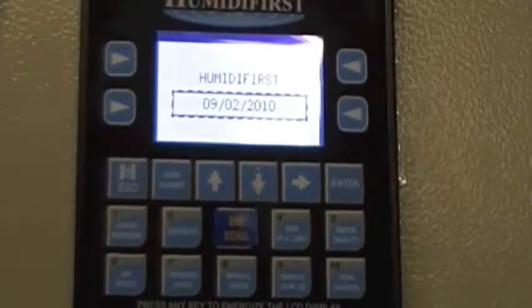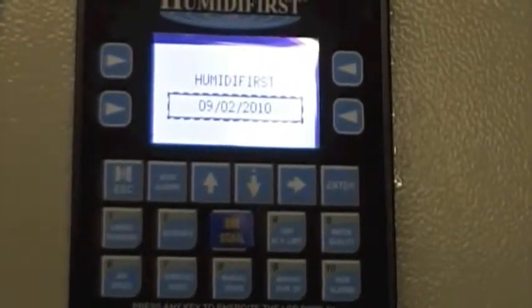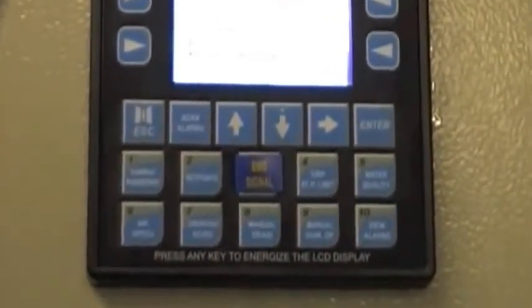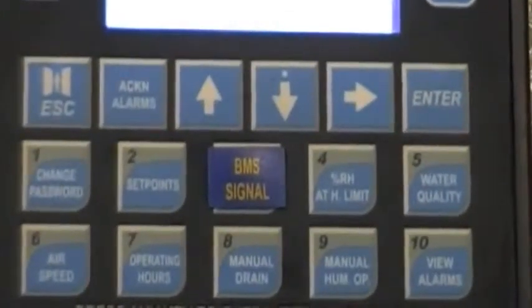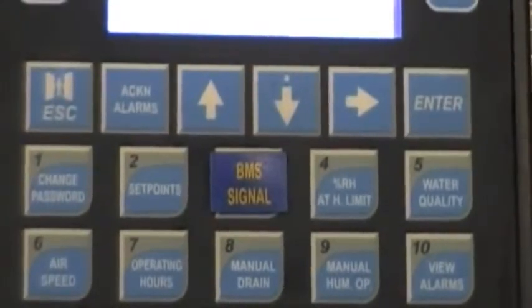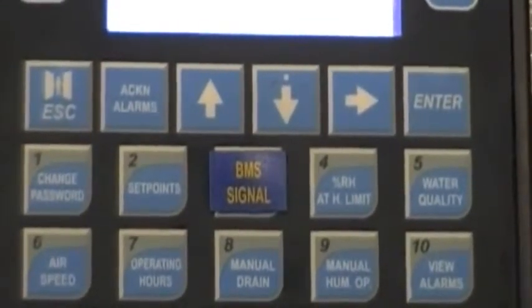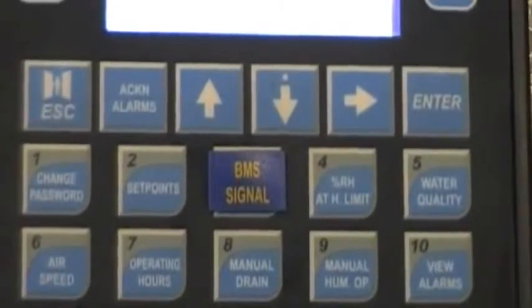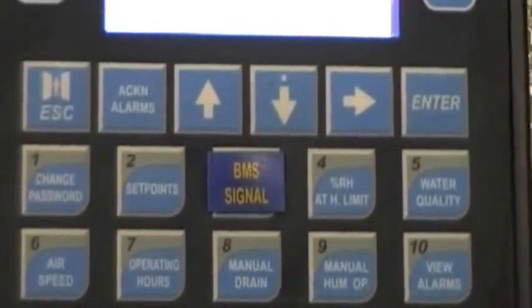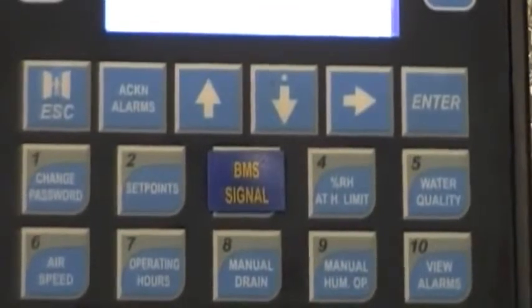We will now take a closer look at your microprocessor. Button number 1 is change password. This allows you to change the password to one of your choice. Button number 2 is set points. This allows you to both view your set points and change your set points. Button number 3 is BMS signal. This will show you your BMS signal and the humidifier's operating percent.